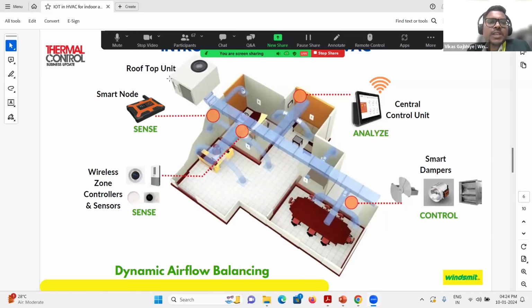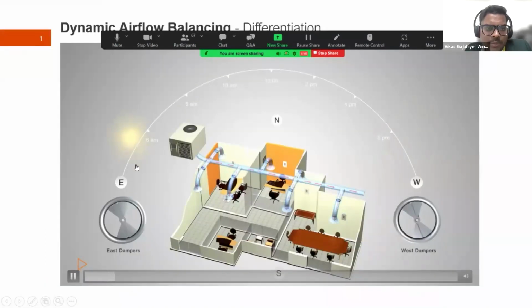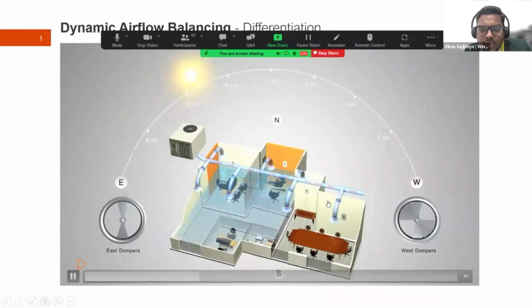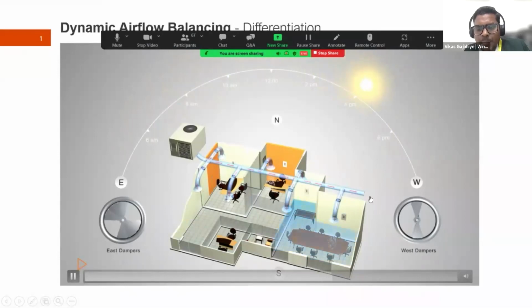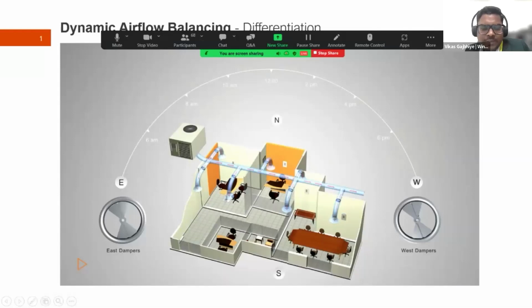If you consider the rooftop unit, it is placed towards the east side. We are considering the placement of the rooftop unit towards the east side, and when the sun moves from the east side to the west side, the damper condition will modulate based on real time data. Now see this animation. The sun is rising from the east side. These dampers are modulating on the basis of sun gain, and the diffusers are opening on the basis of current conditions. Because of this, we can maintain the entire building temperature comfortably and dynamically. That's the meaning of dynamic airflow balancing.